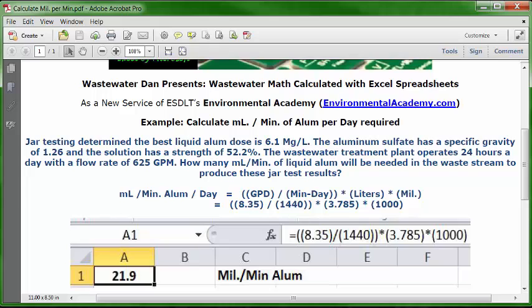Continue the formula: open parentheses, 3.785, close parentheses, multiplication key, open parentheses, 1000, close parentheses, then press Enter. The result is 21.9 — so the answer is 21.9 milliliters per minute of liquid alum, based on the requirements of this problem.